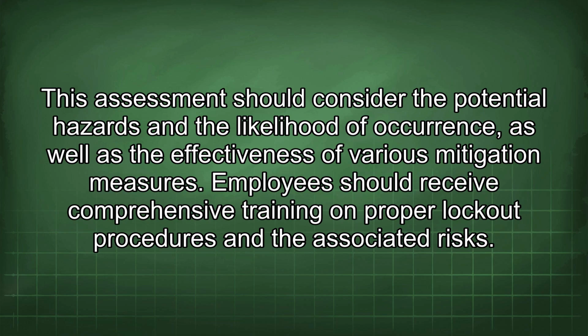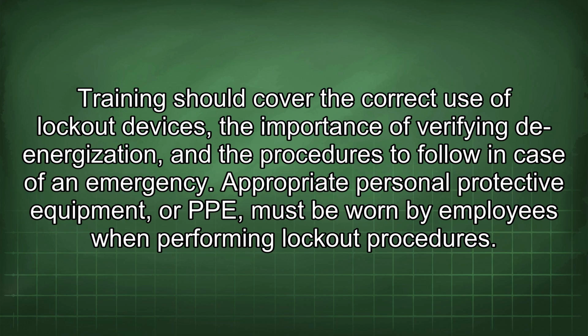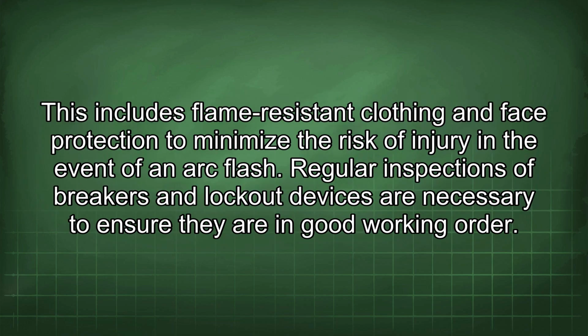Employees should receive comprehensive training on proper lockout procedures and the associated risks. Training should cover the correct use of lockout devices, the importance of verifying de-energization, and the procedures to follow in case of an emergency. Appropriate personal protective equipment, or PPE, must be worn by employees when performing lockout procedures. This includes flame-resistant clothing and face protection to minimize the risk of injury in the event of an arc flash.